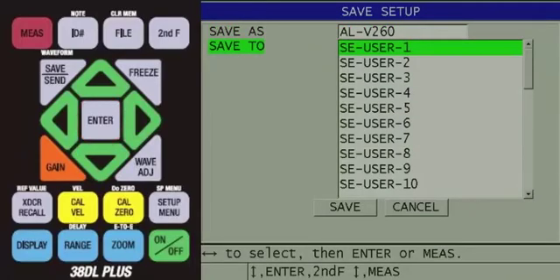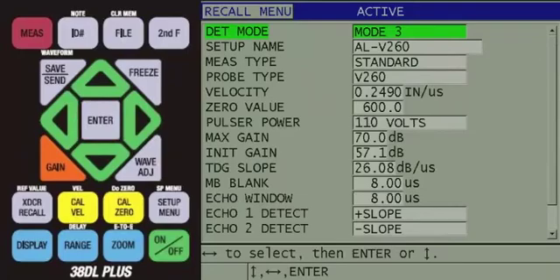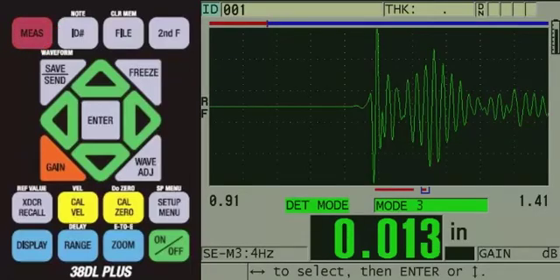Now, the SAVE TO line will be highlighted, and you can choose where to save the custom transducer setup. Use the arrow keys to highlight an available SE user number. Then press the ENTER key so SAVE AS is highlighted, then press the ENTER key again. The active screen showing all the setup parameters will now be displayed. From here, you can press the red MEASURE key to return to the measurement screen.